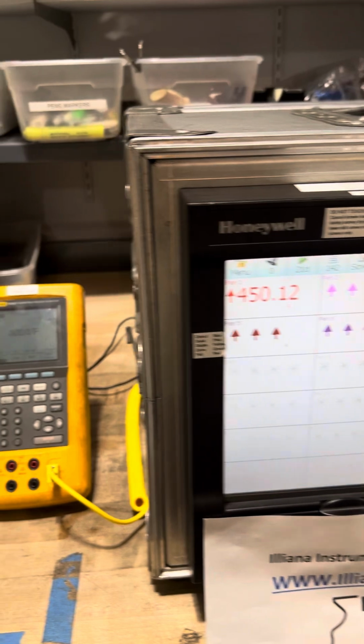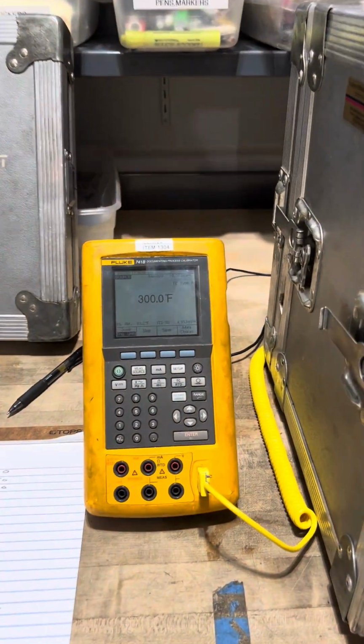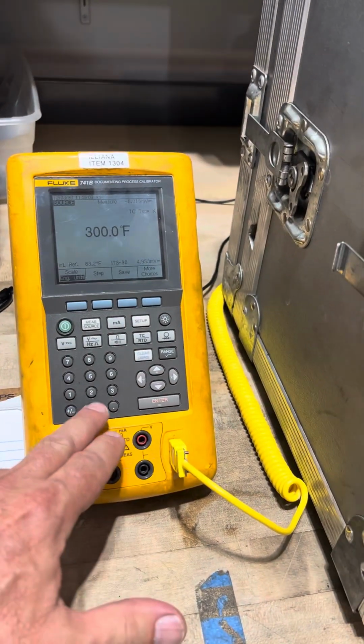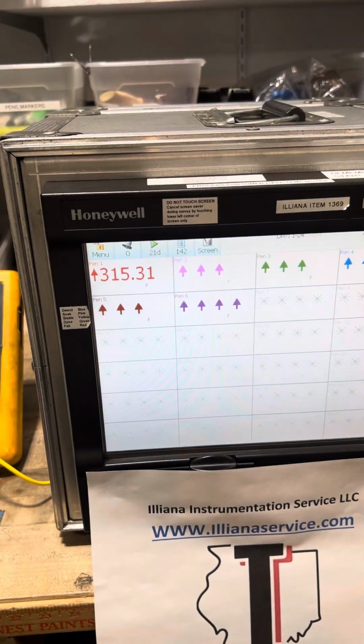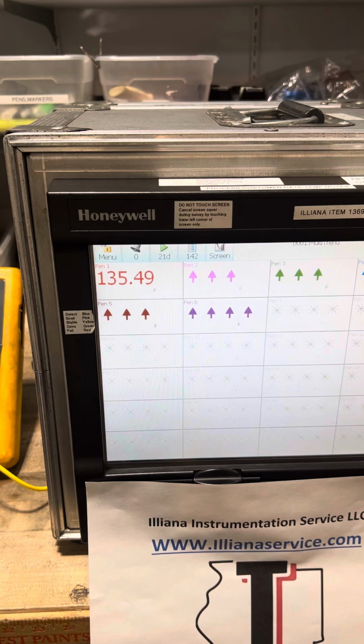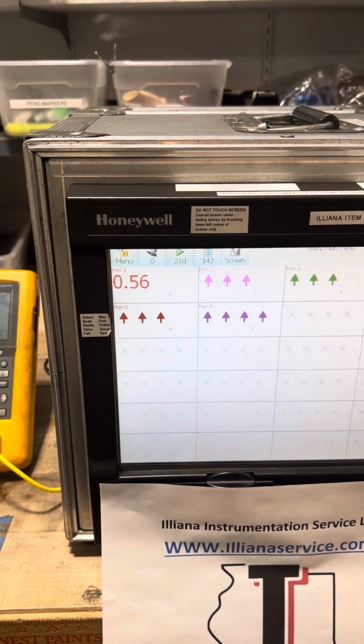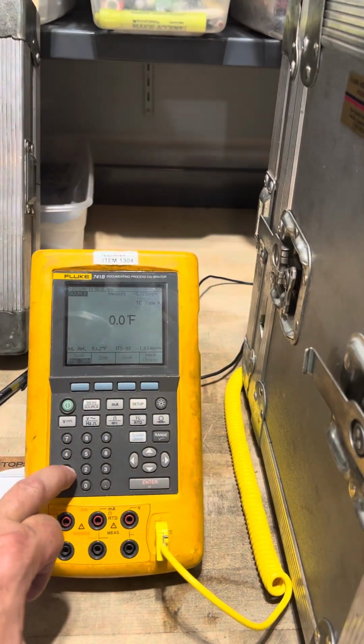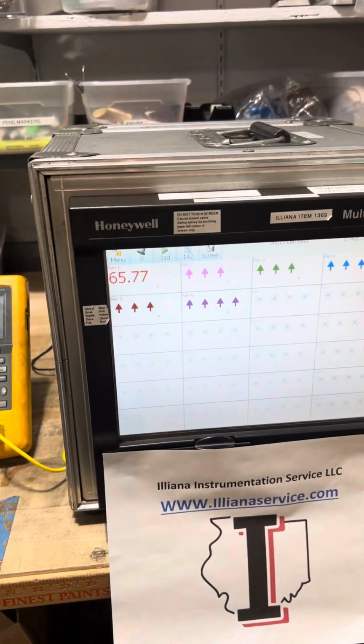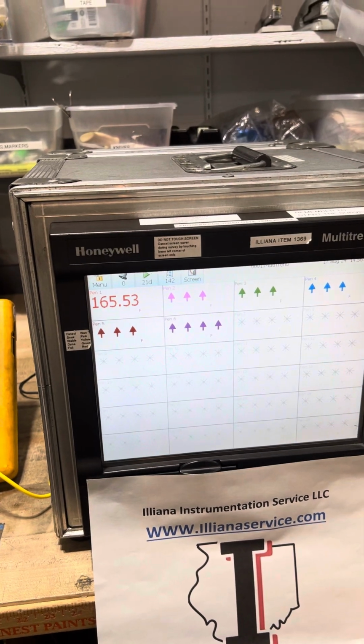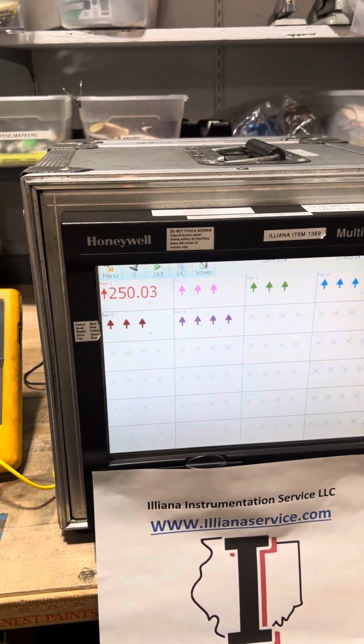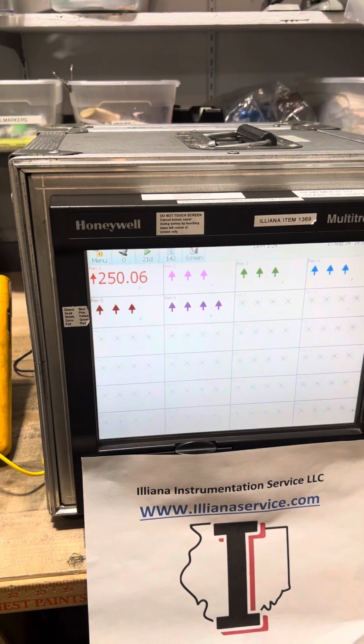So these are just simple math functions. They're linear between the points. So if I go down to 0 right now, as you recall, at 0 I had put in correction factors of 0 on both of those, so the recorder should go reasonably close to 0. And then at 100 I had put in a correction factor of 100 for the recorder and 50 for the wire. So basically it's going to take that 100 and it's going to add the 150 to it, and the recorder will settle in at 250 degrees.